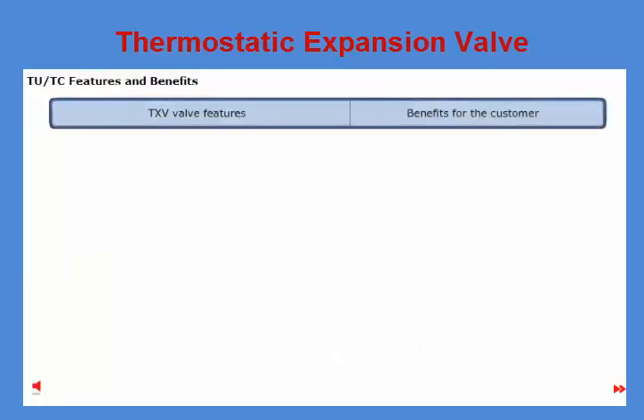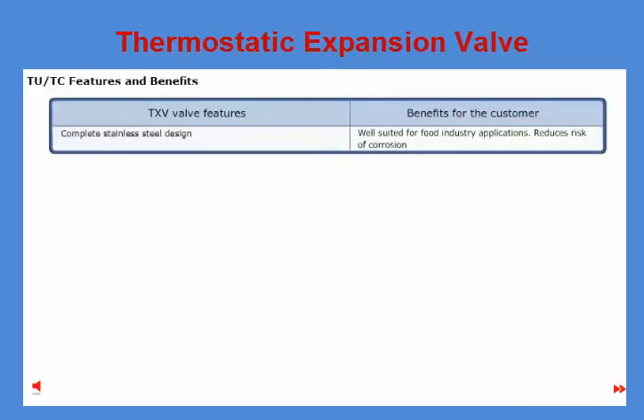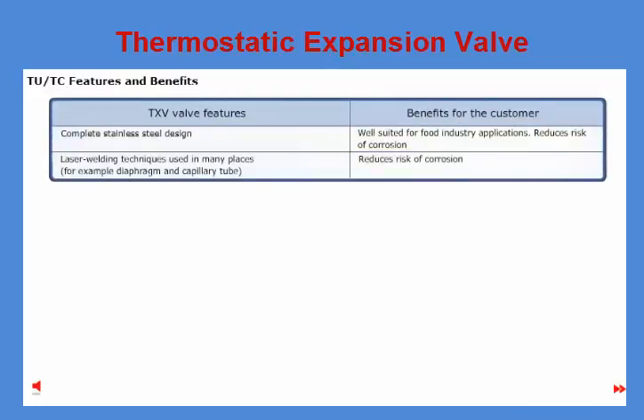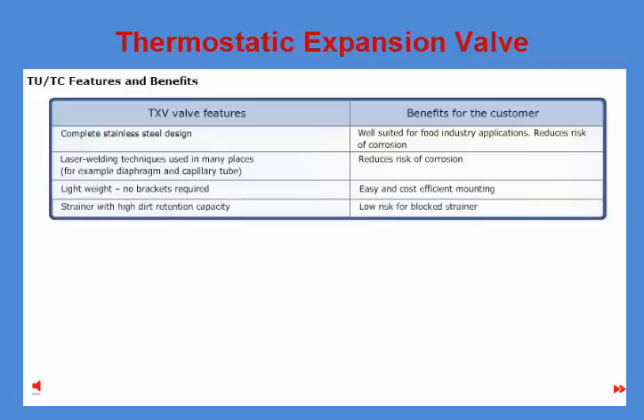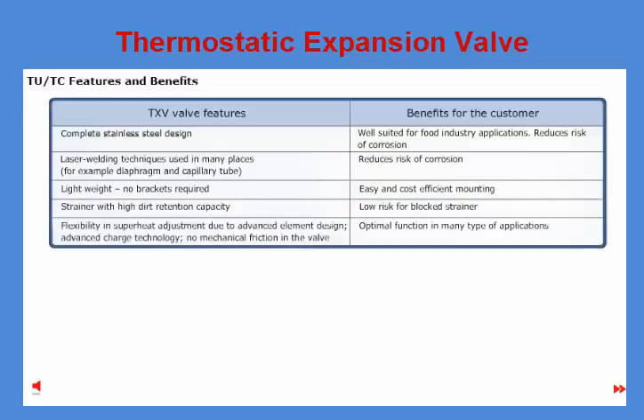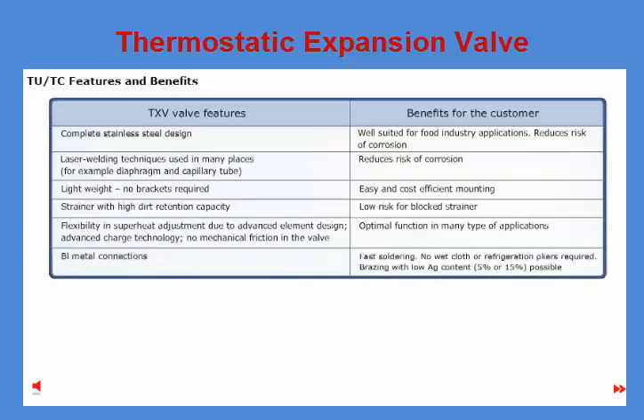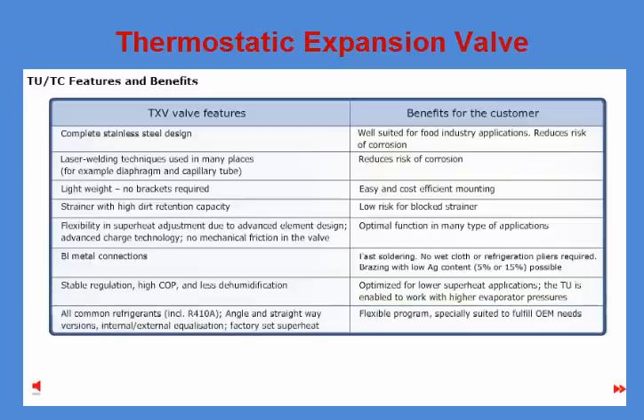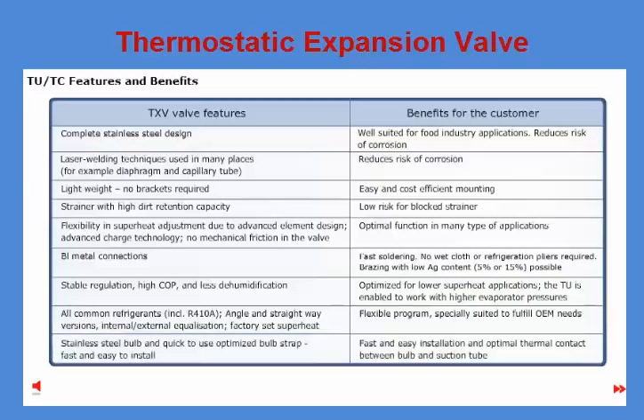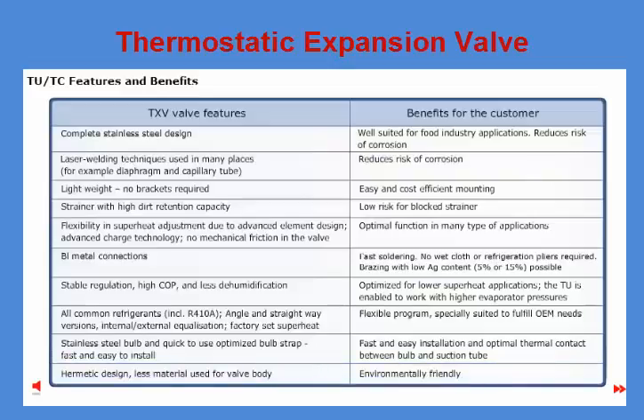General features and benefits of the TU/TC valve include: complete stainless steel design, laser welded techniques used in many places such as the diaphragm and capillary tube, lightweight with no brackets required, strainer with high dirt retention capacity, flexible superheat adjustment due to advanced element design, advanced charge technology with no mechanical friction in the valve, bi-metal connections, stable regulation with high COP and less dehumidification, compatibility with all common refrigerants including R410A, angle and straightway versions, internal or external equalization, factory set superheat, stainless steel bulb with optimized bulb strap, hermetic design, and less material for the valve body.